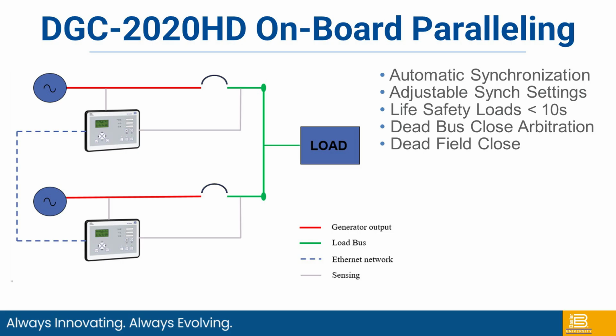Dead field close is if you're in an application where you want to have multiple gens on the bus as fast as possible. What will happen is the DGCs will get the start signal from a transfer switch or switchgear, PLC, etc., and they will first close their generator breakers and then start the unit, and they all come up and synchronize basically as in a slip type of frequency synchronization. And then once they're all online, we start exciting the voltage regulator, and then the voltage builds up. So again, kind of important for life safety loads, especially if you're in need of something that's 10 seconds or less for NFPA 110. Dead field close works very well.